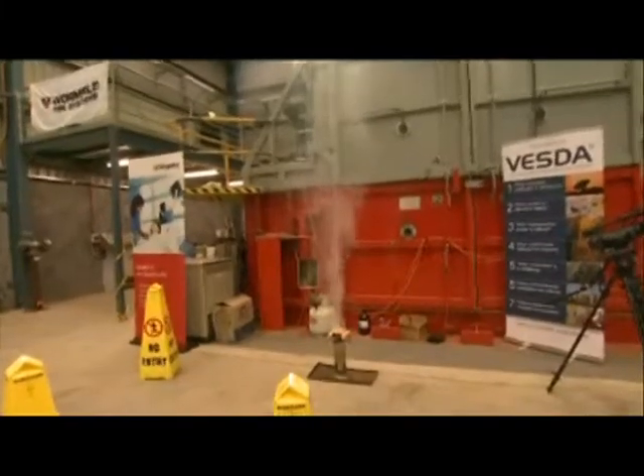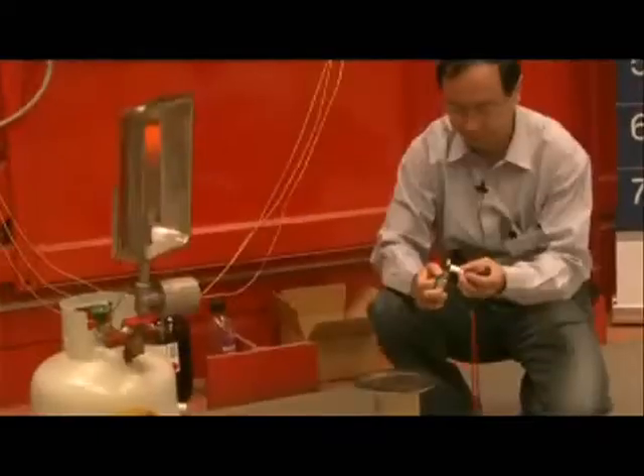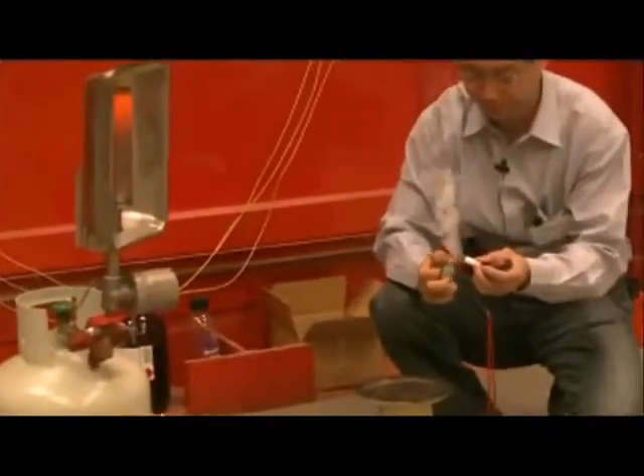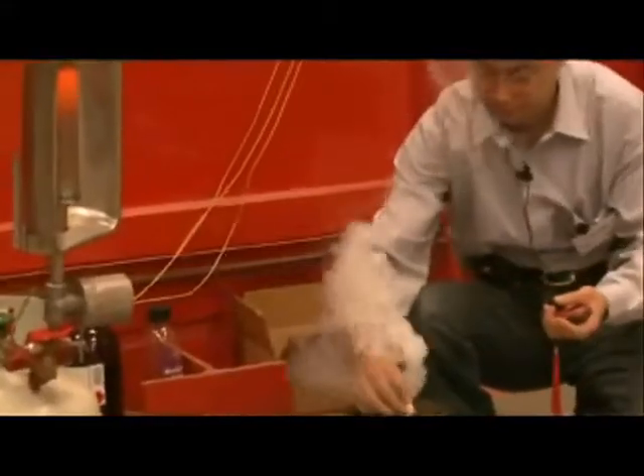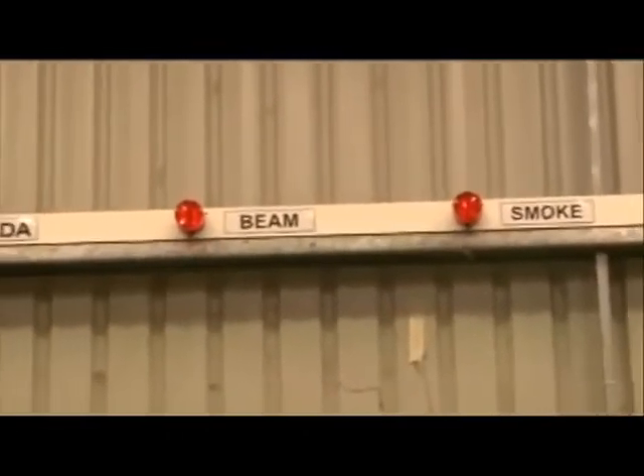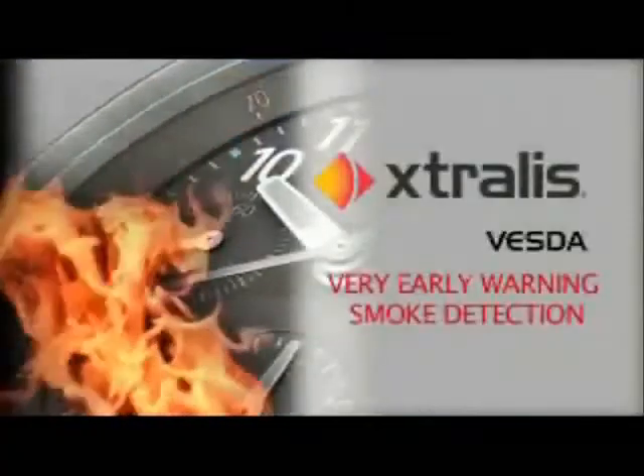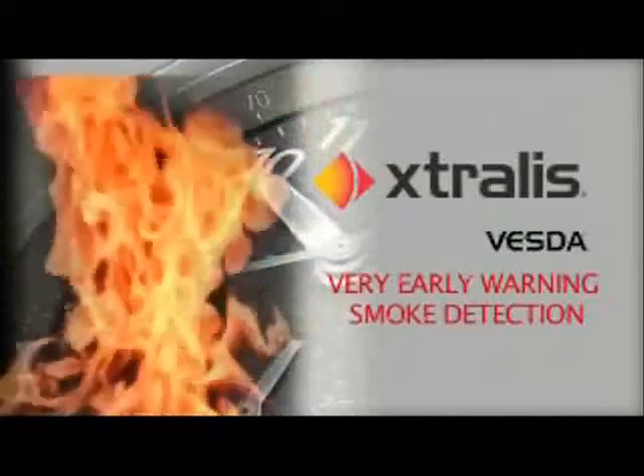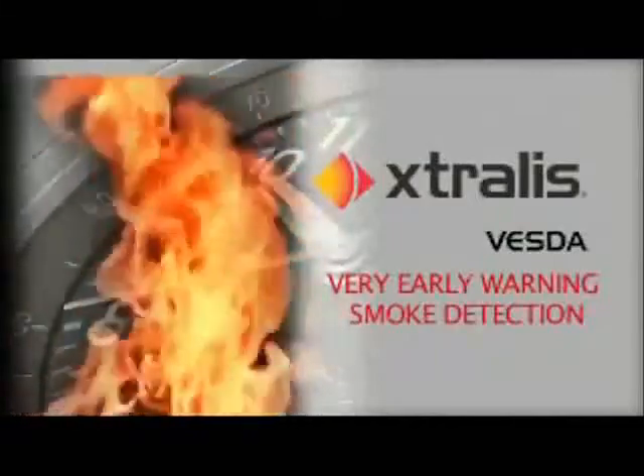In each of these tests, the VESDA system detected the presence of smoke and raised the alarm while the fire was smouldering and quite manageable. In most of the tests, as can be seen from the formal test results, the point and beam detectors had not detected any smoke and the fire was already at flaming stage. These tests proved once again that VESDA early warning smoke detection systems are the reliable choice for the early detection and prevention of a major fire.